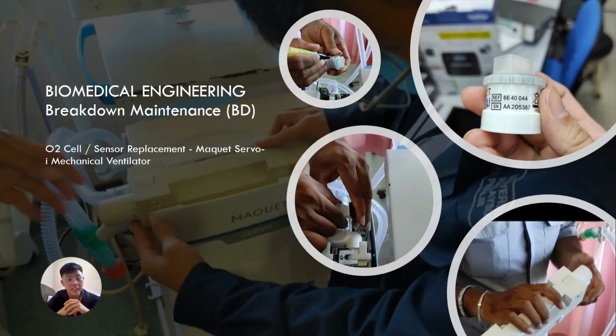For the second breakdown maintenance, it was necessary to replace the O2 cell, or the oxygen sensor, in the mechanical ventilator. The previous one was a mechanical ventilator with model Servo S. This is a Servo I mechanical ventilator, two different ventilators.